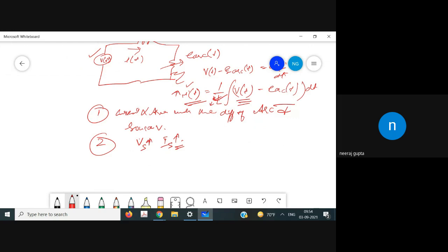So the fuses that can be used can be the power class fuses or the distribution class fuses. They are quite different in rating. If you take the case of the power fuses, they have a high X by R ratio. This issue is encountered because X is high in that very case.